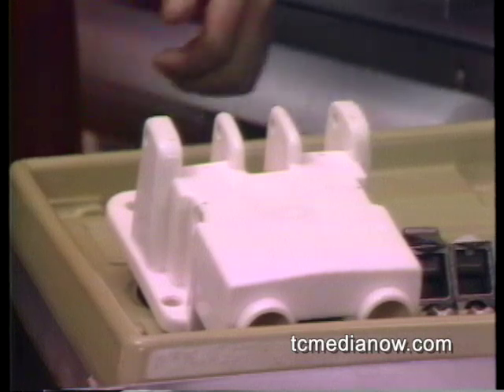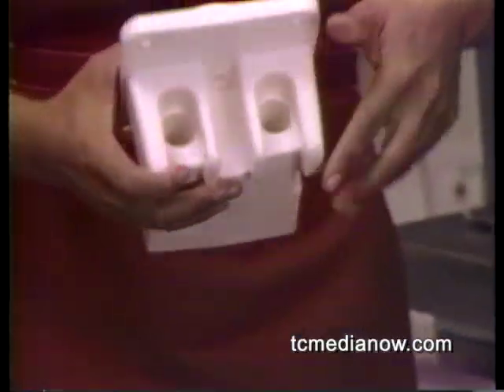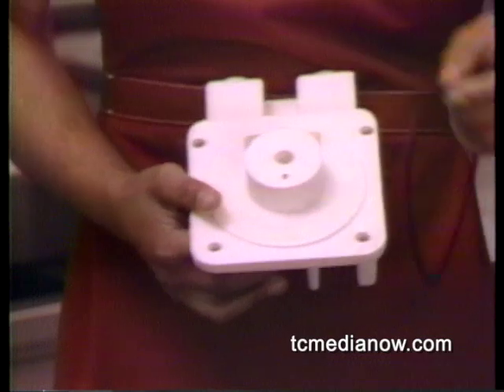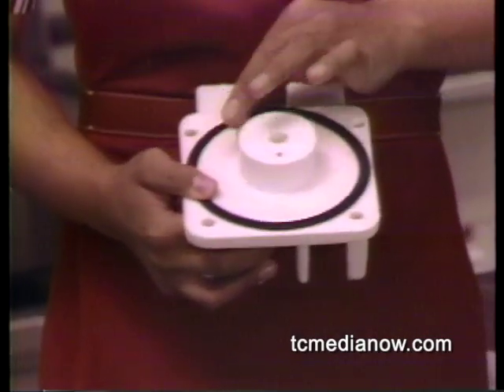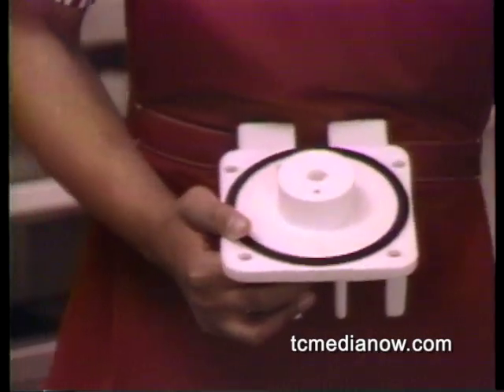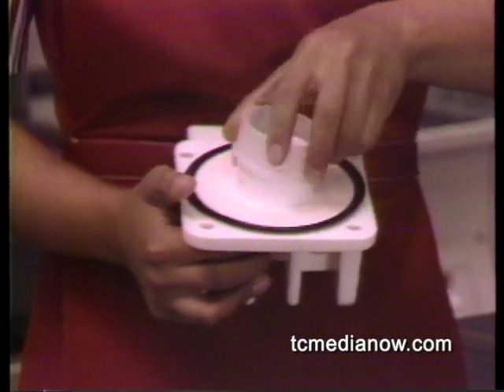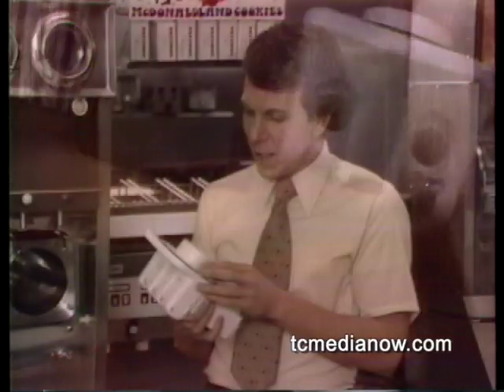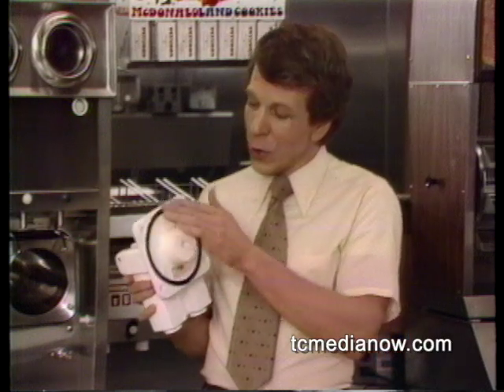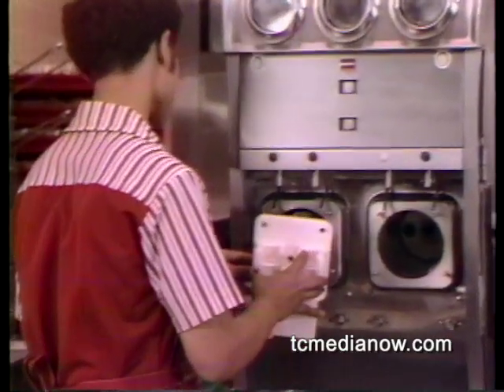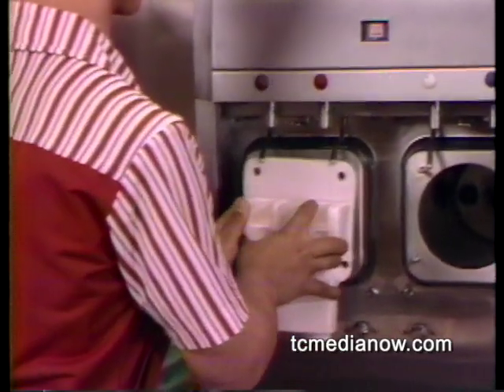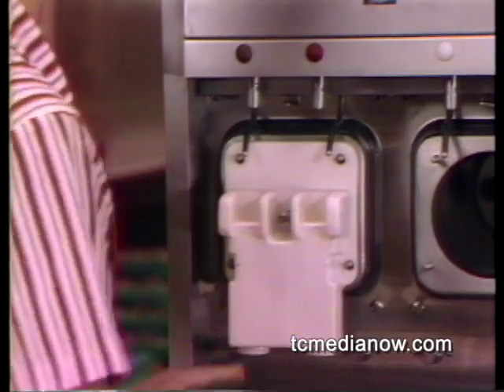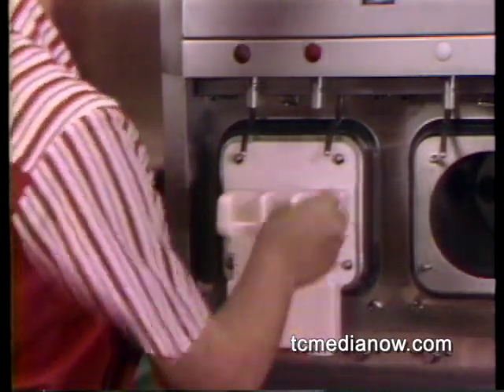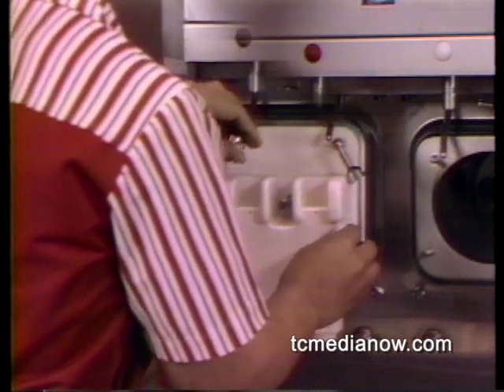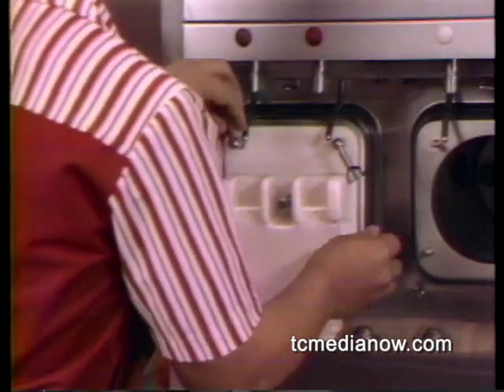Next, pick up the freezer door and install the door gasket and the sleeve bearing. Position the sleeve bearing so the flange edge is against the door. Just to warn you, don't lubricate either of these parts. Now you can position the door so the torque rotor shaft and the 4 door bolts are in position, and secure the door by tightening the door fasteners in a crisscross fashion. Make sure you don't over-tighten the door fasteners.